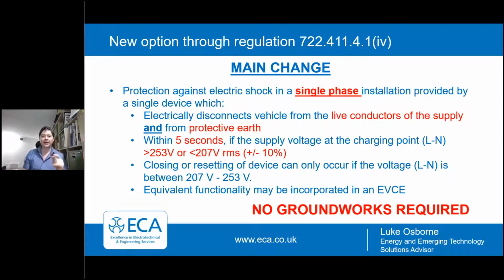It's important to point out here there have been a couple of issues with solar PV when using these. As mentioned, if the voltage that is being seen at the incomer to these devices exceeds 253 volts, the charge point or the protective device will turn itself off. Sometimes, if the building is sited close to a substation, or has high incoming electricity, and also has solar PV on the property, in order for the solar PV to export its energy, it raises the voltage slightly above that coming into the building. In certain instances, this may cause that voltage to exceed 253 volts, in which case the EV charge point would turn off, and then the customer wouldn't be very happy.